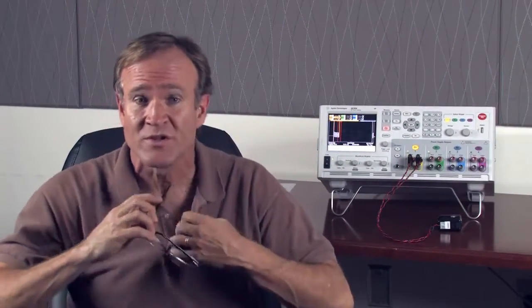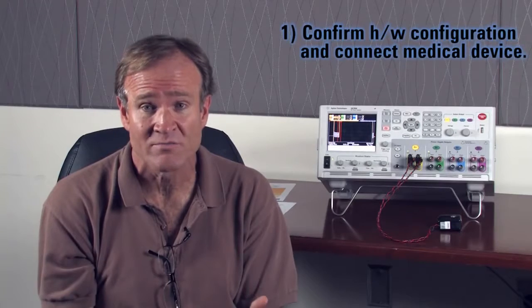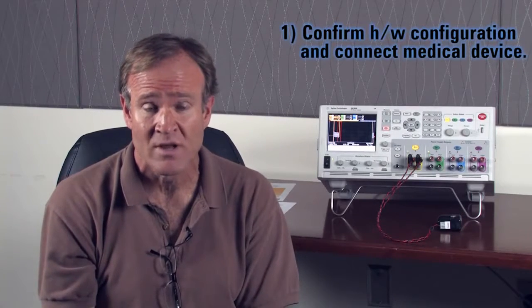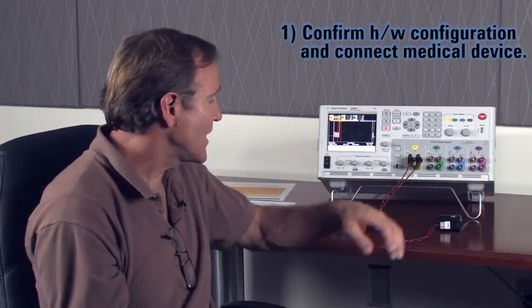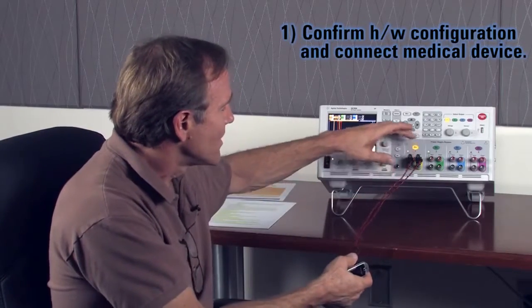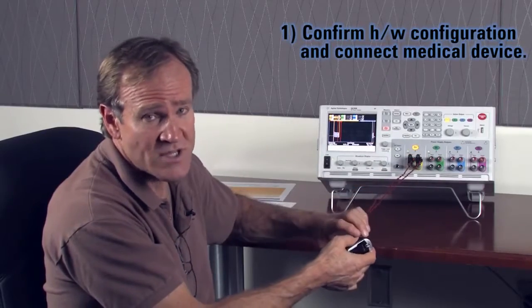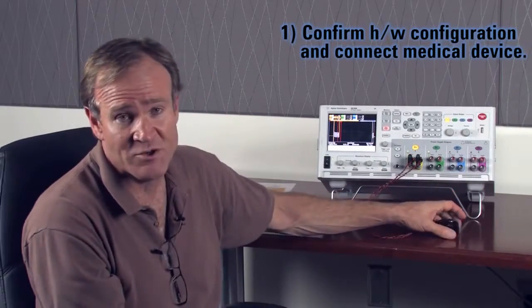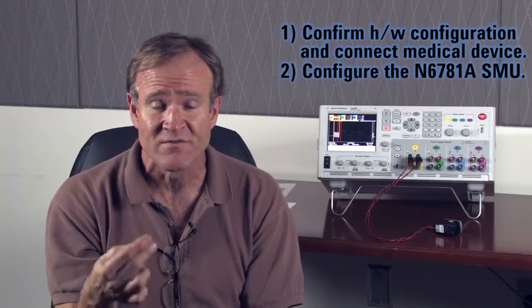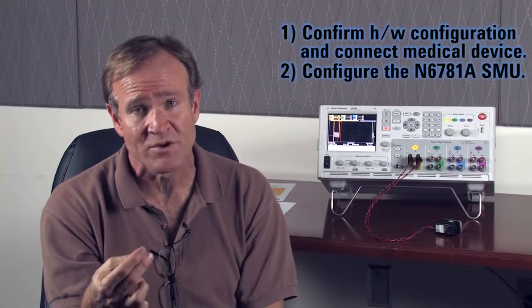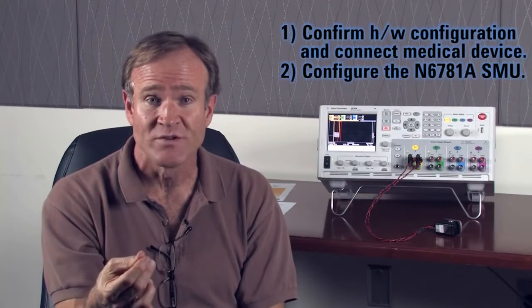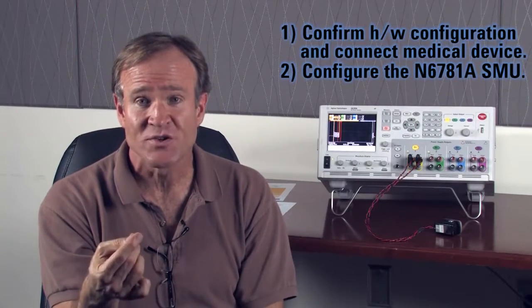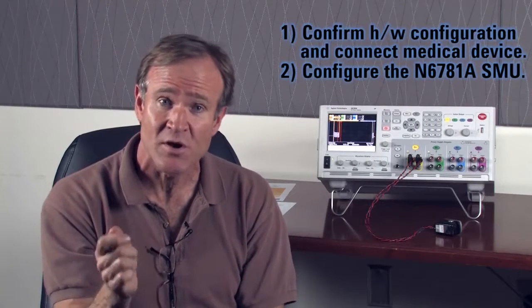So now that we've done that, what I want to do is go back through these 5 steps and give you some suggestions of things that you might want to do as you look at your own medical device. So first of all, you want to make sure that you've got the right hardware. We talked about that. You need an N6781 SMU. And then as you're connecting your device, I suggest you use both source and sense. Do the remote sensing out to the device so you get the most accurate measurement. Second, step 2 is configuring the SMU. The main thing to remember when you're configuring that is outputting the voltage that you expect and making sure that you have the output voltage bandwidth set to low.